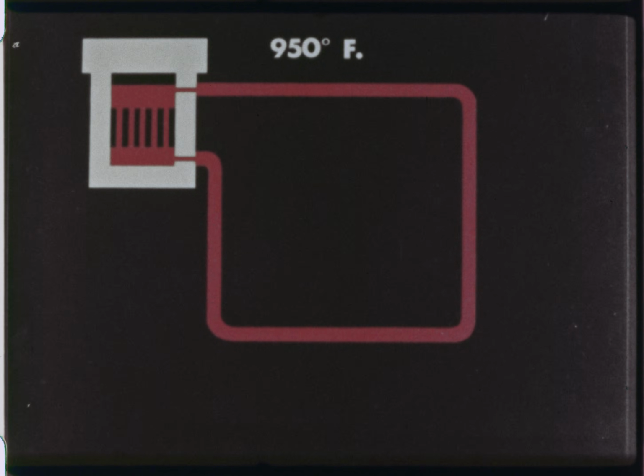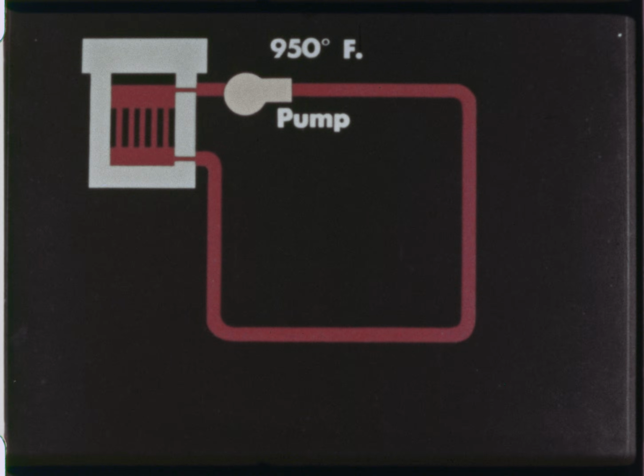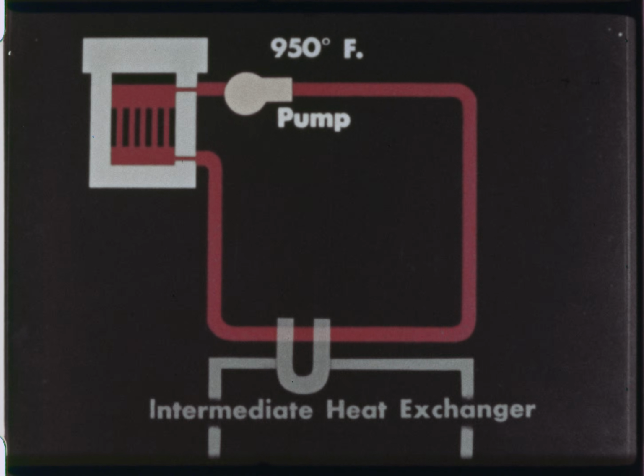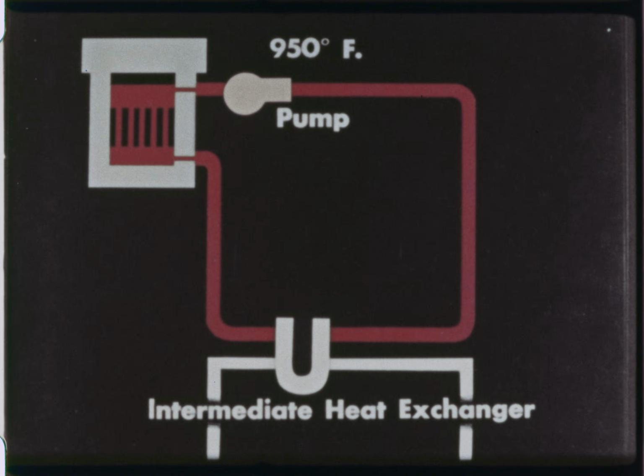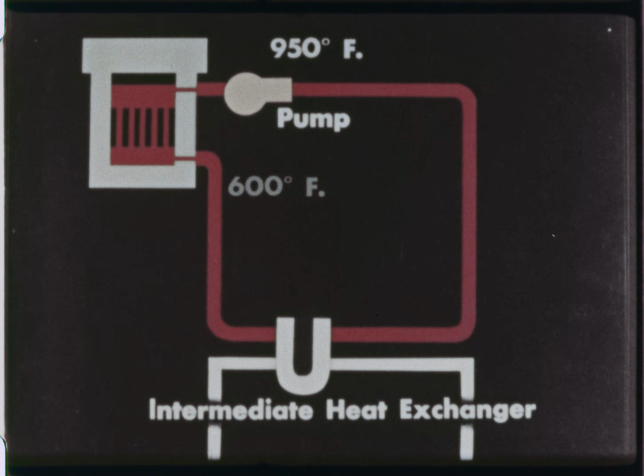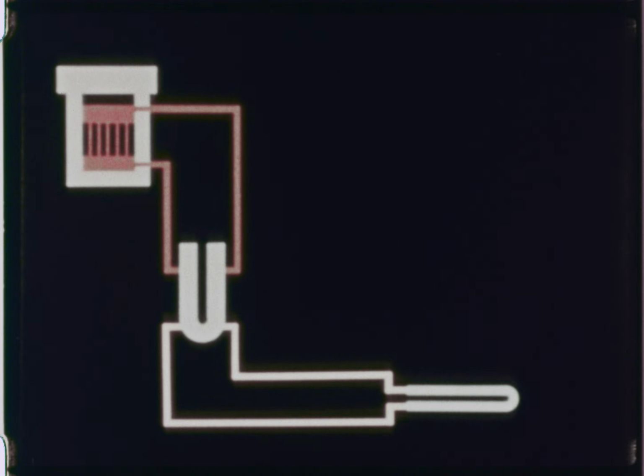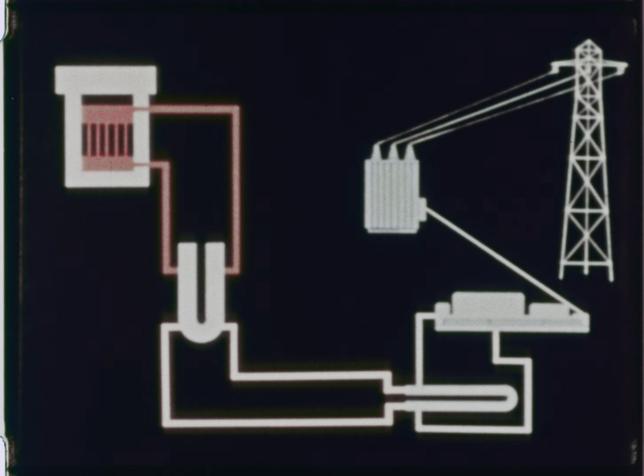The primary sodium coolant becomes radioactive during its passage through the core. This radioactive sodium is pumped through 3 identical primary loops to intermediate heat exchangers and returned to the reactor vessel at approximately 600 degrees Fahrenheit to repeat the cycle. The heat carried by the sodium in the primary loops is transferred by the intermediate heat exchangers to the 3 secondary sodium loops, which are non-radioactive.